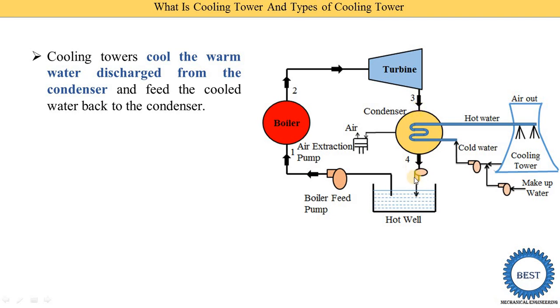How is this steam condensed? This steam is condensed by using cold water. This cold water is supplied through the pipes and it absorbs the heat energy from the steam. When this cold water absorbs the heat energy of the steam, the temperature of the water increases. This hot water from the condenser outlet is then supplied to the cooling tower.